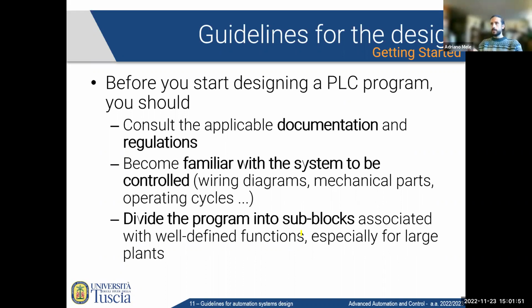Third, divide the program into sub-blocks associated with well-defined functions, especially for large plants. This connects to the design cycle from a previous lecture: you want to design your plant top-down, dividing it into small parts, programming those parts, and then coordinating them to form the full automation system, rather than one single giant program. This makes code more readable, reusable, and documented at a lower level, so you know what each part does. Of course, you need a happy medium: not a separate function for everything, but also not a single program for everything. You need to subdivide your software efficiently.